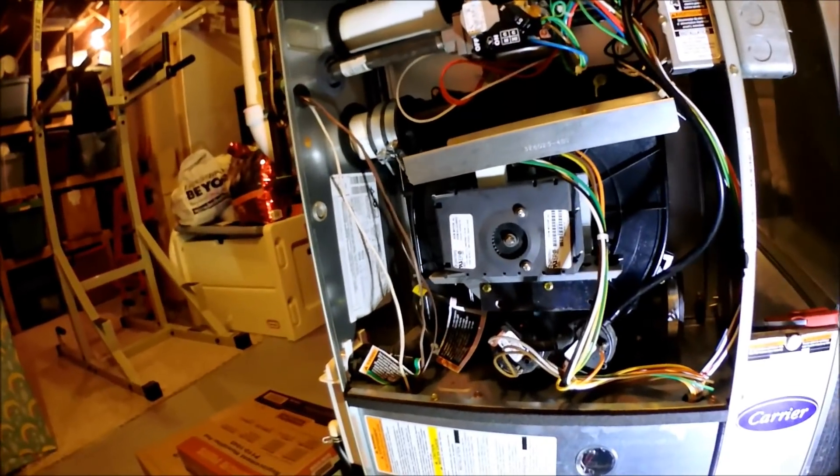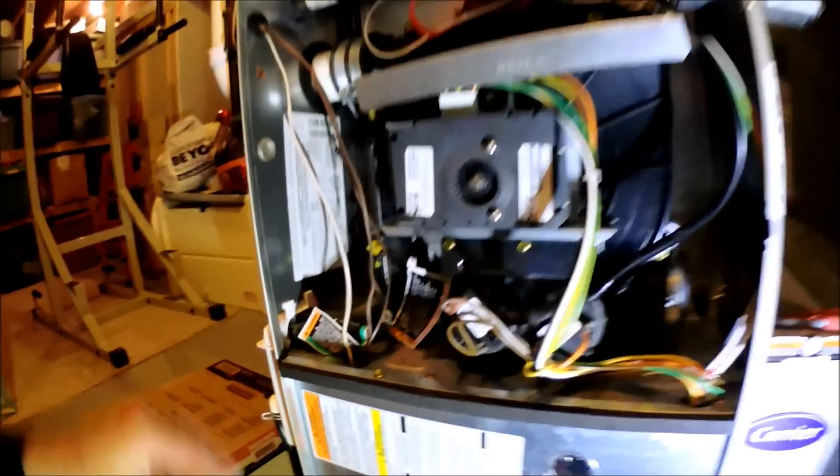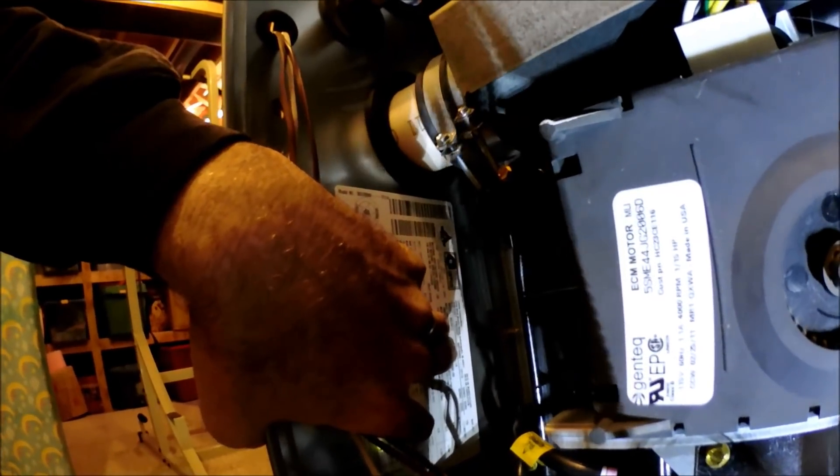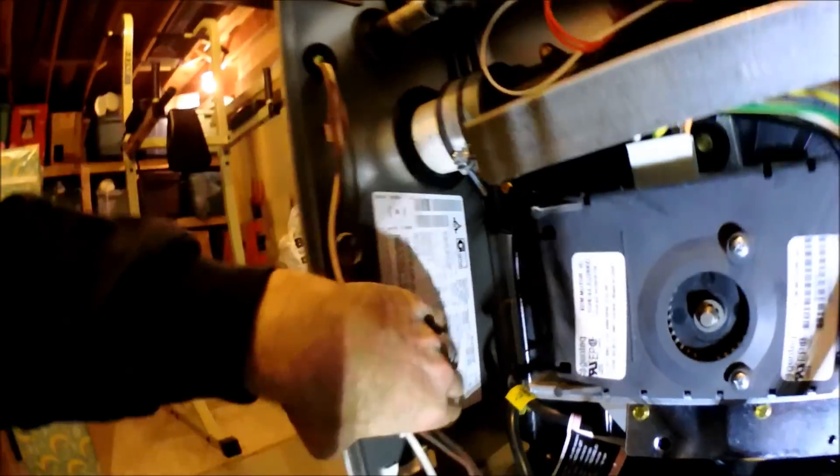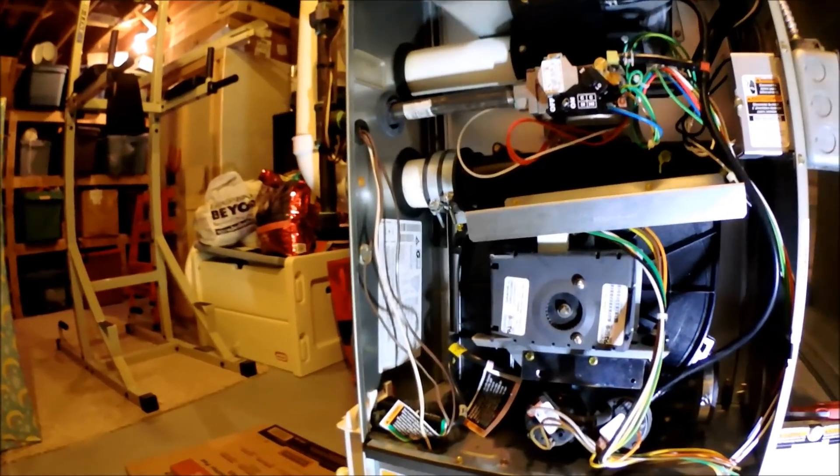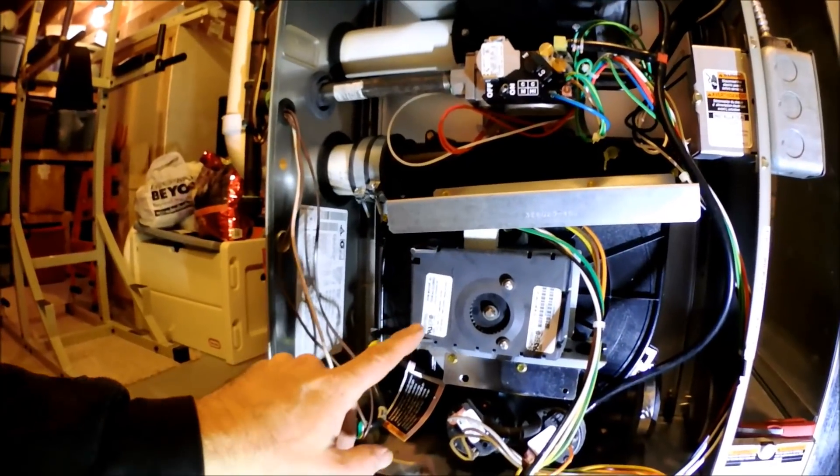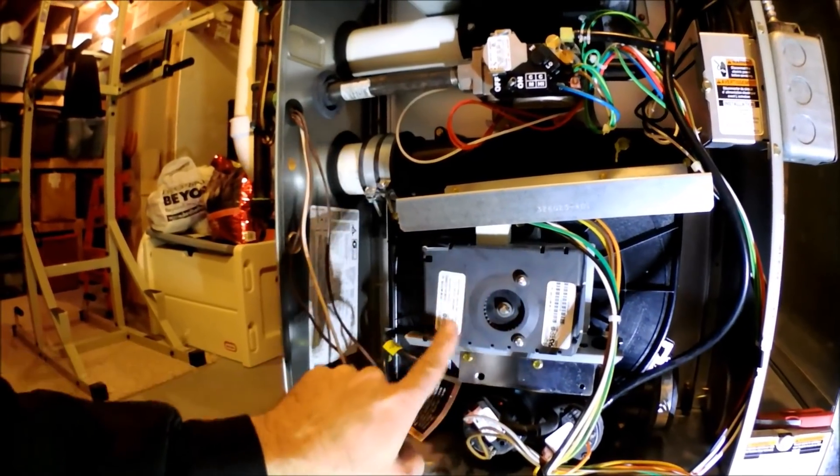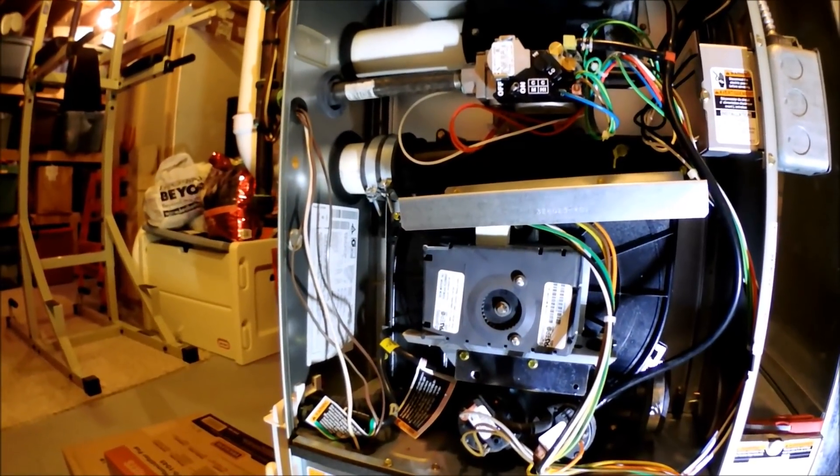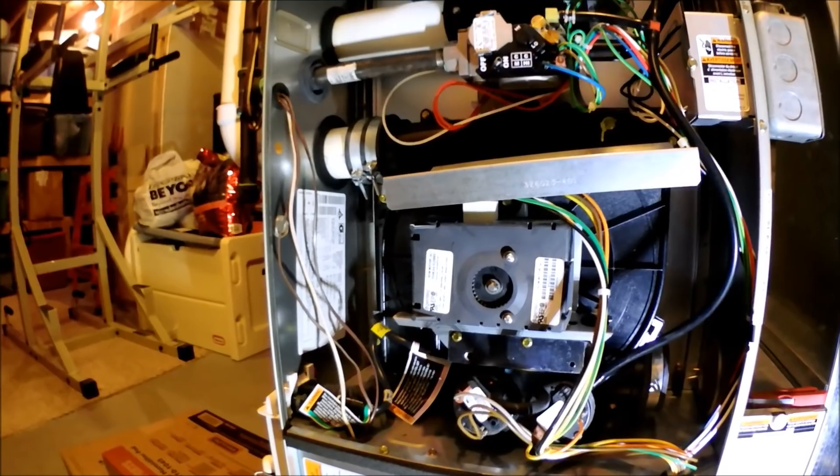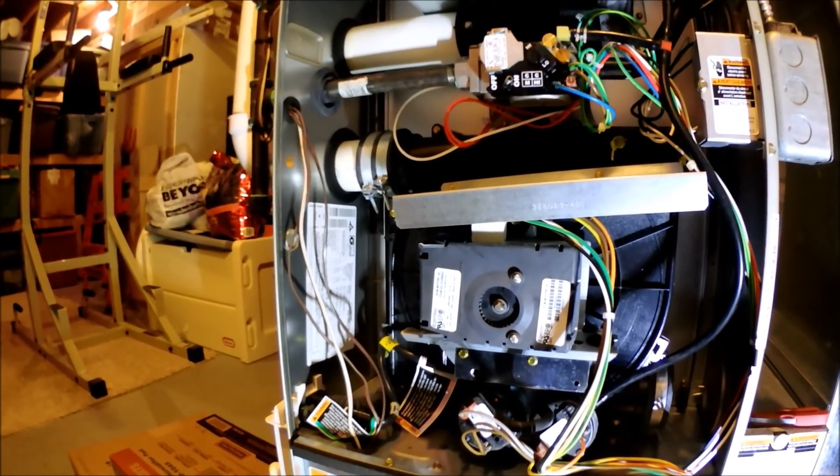Today we're working on a Carrier 58UVB 60-060 from 2011. Over the years we've had problems with these variable speed inducer motors that get loud, so what we're going to do today is replace it.